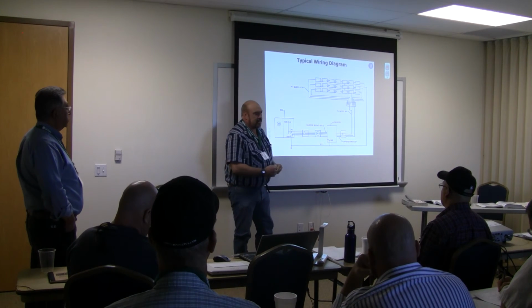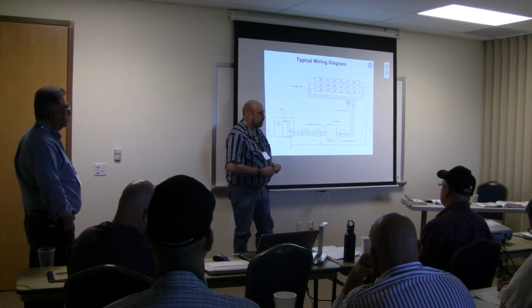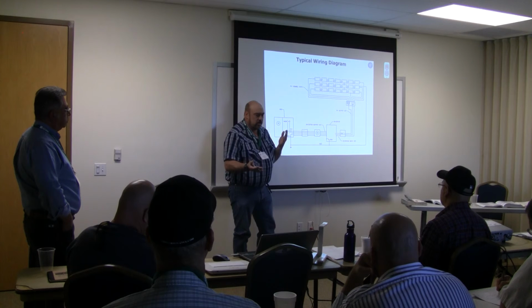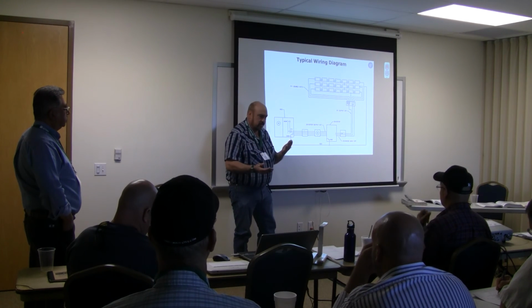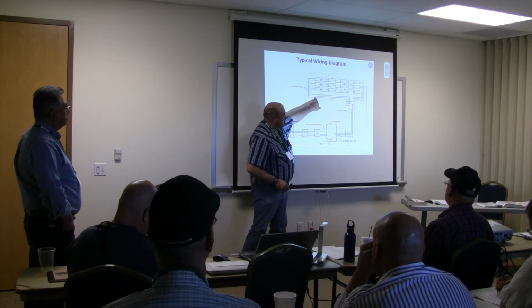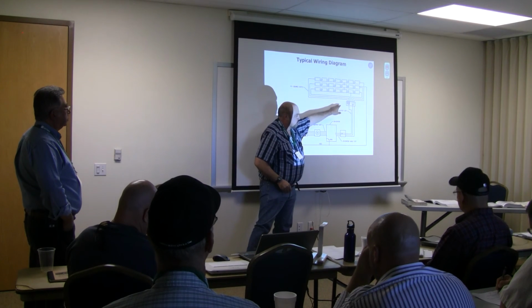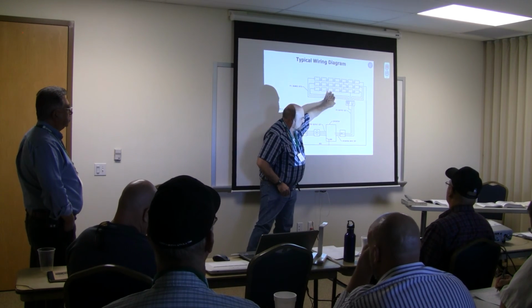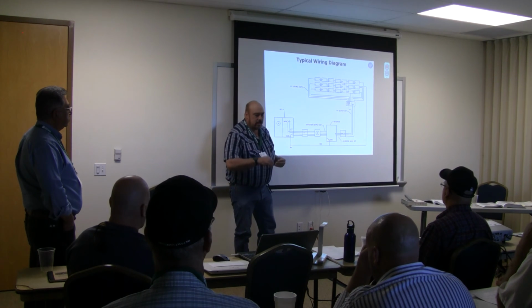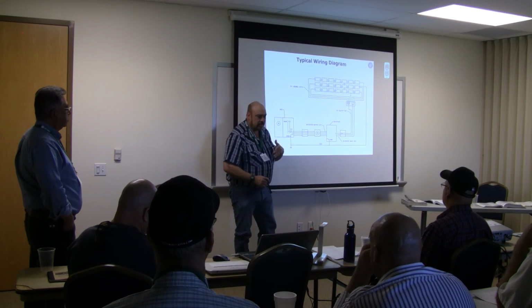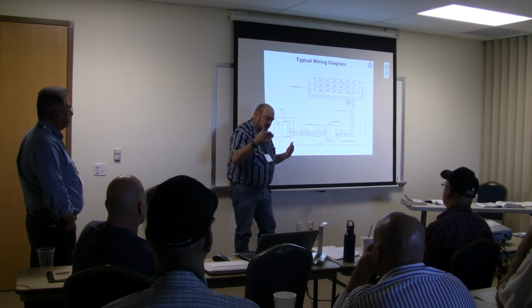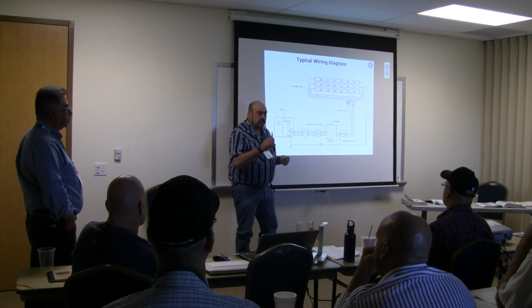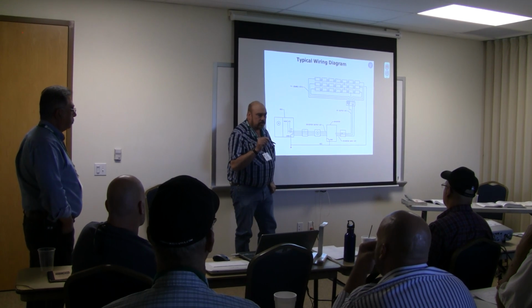So you're going to do those conditions of use to determine the size of conductor here. Now 690.8, they changed it in 2011 where they give you two options, and you have to go with the one that's the worst case scenario. You can go 125% times 125% to figure out the size of these conductors. If not, if that isn't the worst case scenario, then your conditions of use, which you're going to have to do a number of other calculations. They should have all of that done for you.